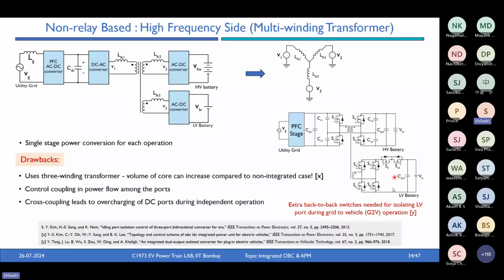It would mean that even though you're not sending power, you have losses. So those are the challenges which exist in this approach. Interestingly, some authors have also reported that when you use a three-winding approach, the volume of the combined three-winding transformer core can in fact be higher than when using a non-integrated design with two separate transformers. This would probably differ from one design to another, but it's certainly not generally true that an integrated approach gives you a smaller transformer size compared to a non-integrated design.